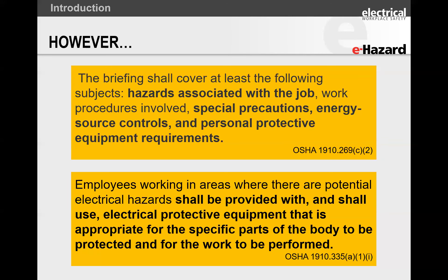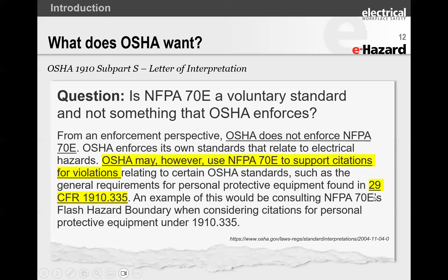What if you are not in power generation? For other users, it says employees working in areas where there are potential electrical hazards. If you have not done your risk assessment, how do you know that you have a potential electrical hazard? These folks at NFPA 70E do a fantastic job of the risk assessment. You don't have to follow the standard if it legally doesn't apply to you, but that doesn't mean you shouldn't use it. There's a golden nugget in the standard — the risk assessment portion within 70E. I found a letter of interpretation stating that OSHA will not enforce NFPA 70E, but they may use it to support a citation.